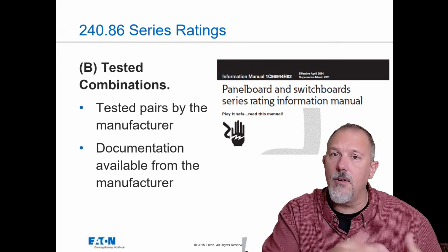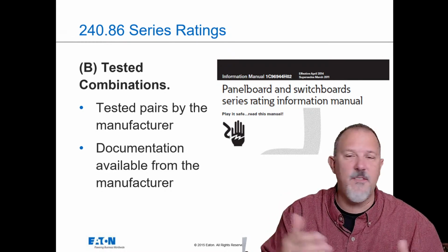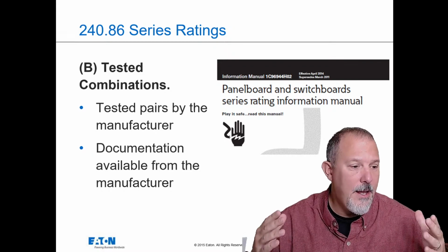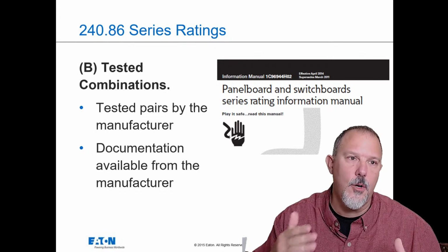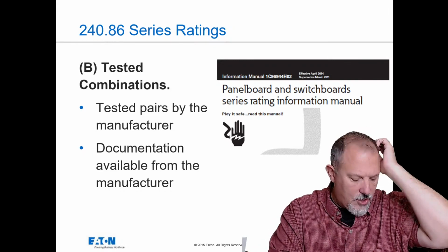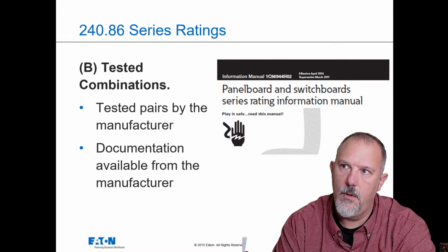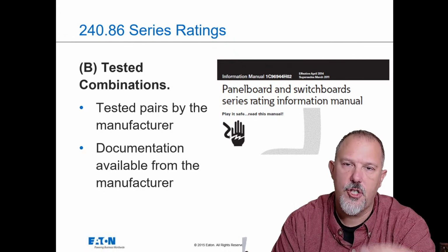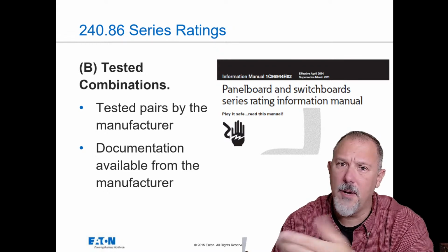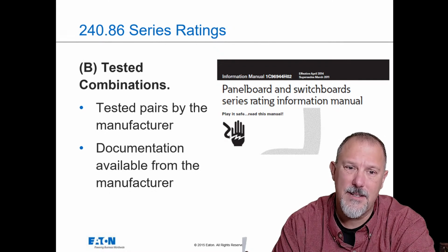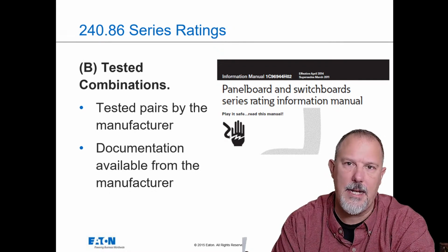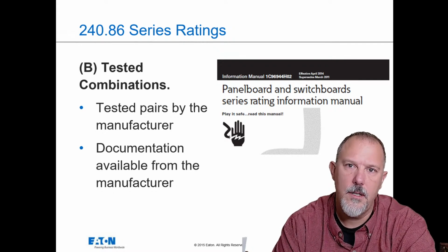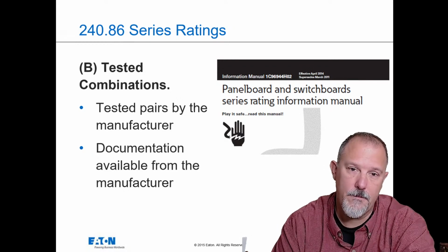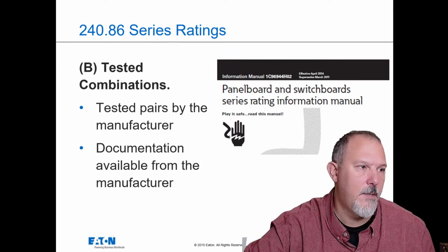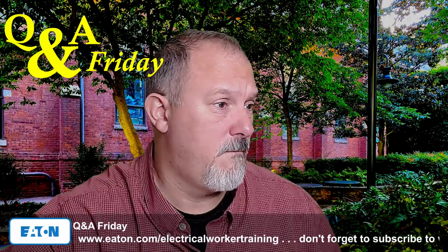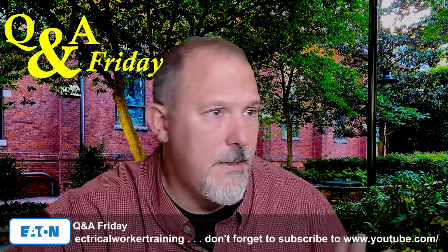And now, if it's a power circuit breaker, obviously I have an instantaneous that would be high enough. But I'll tell you, if it's a circuit breaker, to say that it's not going to be going into an active mode like it says here, that it's going to remain passive, you would have to show that your clearing time is so fast that you're below the trip curve of the circuit breaker. And then I would argue you're probably not exceeding the interrupting rating at that point. Just think about it. You're exceeding the interrupting rating, which means you're well into the instantaneous of that circuit breaker. I don't know how you can do it outside of a tested pair. So, long-winded way to answer that one, but that's all I have to say about that. Hopefully that helps. I don't know if it did or not, but it was the best I could do with what I got.